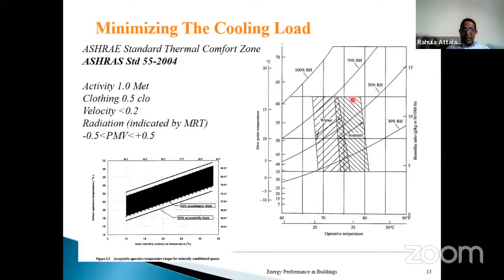And this has been established by a large number of tests carried out by ASHRAE. The target for the starting point of the cooling load is that your interior conditions should fall within this zone. And if it is a ventilated building, your interior temperature should fall, based on the outdoor temperature, within this zone. So the standard will indicate how your interior condition should be decided, and based on the interior condition, you will have to decide what the cooling load is. For the cooling load, the starting point would be the internal temperature and the humidity that you are going to make use of. And that's why standard 55 is important in deciding the cooling load.